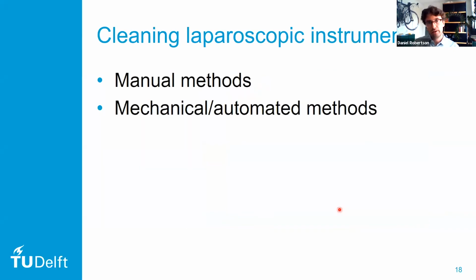Now, in cleaning laparoscopic instruments, we can generally divide it into two main methods. We have manual methods and we have mechanical or automated methods. Now, the automated methods are generally things where you need a washer and disinfector machine or ultrasonic cleaners. These machines make the cleaning of the instruments much more effective. But because we're focusing on rural settings, I'll focus on the manual methods.